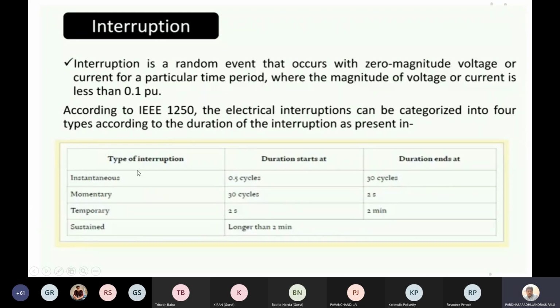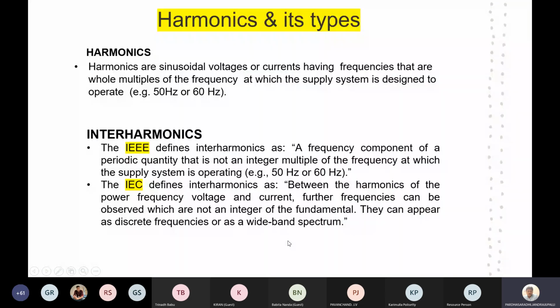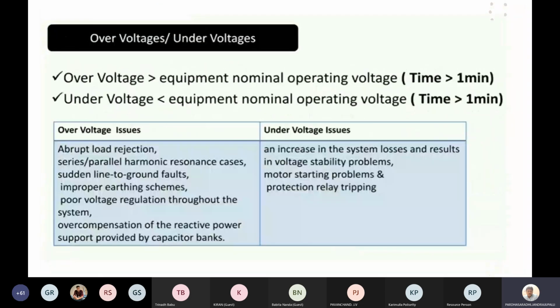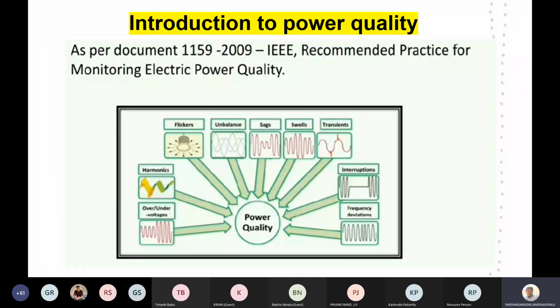If the problem is instantaneous, it is between 0.5 cycles and 30 cycles. Momentary means the duration starts at 30 cycles and ends at 2 seconds. Temporary means it starts at 2 seconds and ends at 2 minutes. Sustained means it is longer than 2 minutes. So this is what we discussed. As we already know, we covered over voltages, under voltages, harmonics, unbalance, sag, swell, transients, interruptions, and frequency deviations.